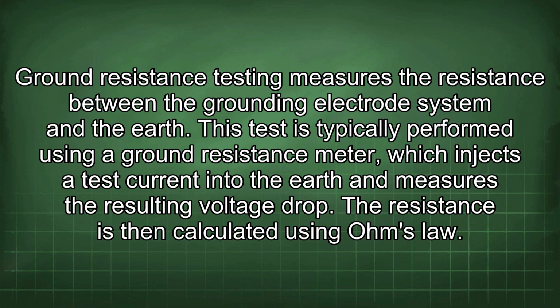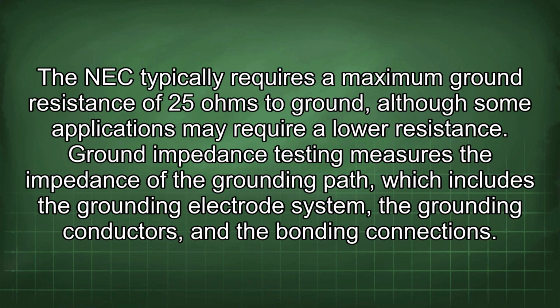Ground resistance testing measures the resistance between the grounding electrode system and the earth. This test is typically performed using a ground resistance meter, which injects a test current into the earth and measures the resulting voltage drop. The resistance is then calculated using Ohm's law. The NEC typically requires a maximum ground resistance of 25 ohms to ground, although some applications may require a low resistance.